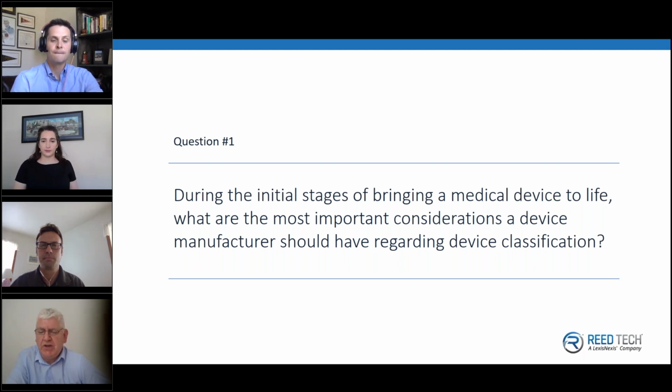Yeah, one thing I'd add on that, Rachel, is that the GMDN is designed so that one term should describe the product you've got in front of you, whereas the pro codes, the FDA pro codes, are more attribute related, and you might have more than one for your particular product, depending on the particular type of product and the way it's designed, the way it's maybe packaged. So that's something to be aware of. You might find you have 2 or 3 pro codes for your product, but you should only really have one GMDN term that describes the particular product you have in front of you.